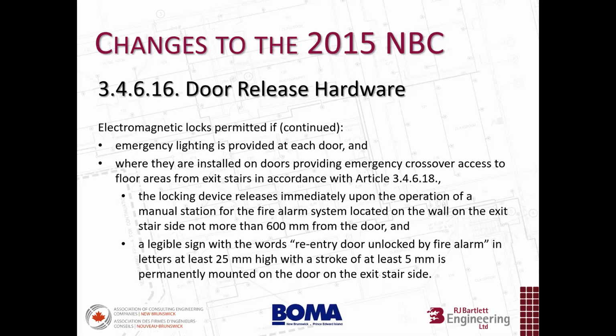So if I find myself in an exit stair and I'm looking to get back into a floor area, but on the door providing access back into the floor area there is one of these devices with an electromagnetic lock, I'm required to be provided with a pull station and some signage on the door. The locking device releases immediately upon the operation of that pull station. It has to be located on the exit stair side of the door, not more than 600 millimeters from the door. And the signage on the door is required to say re-entry door unlocked by fire alarm, with sizing requirements as well.